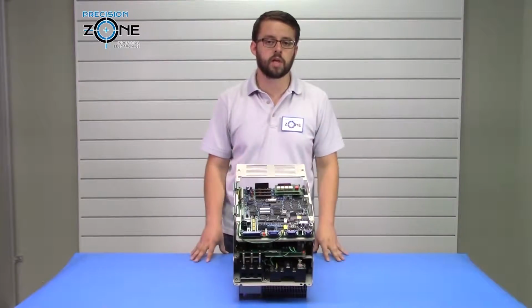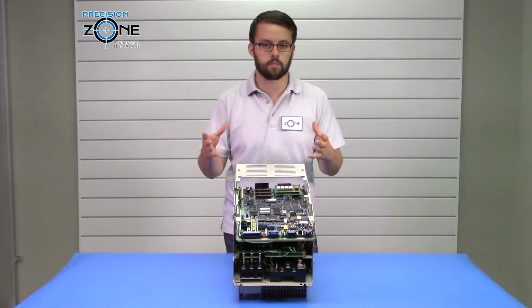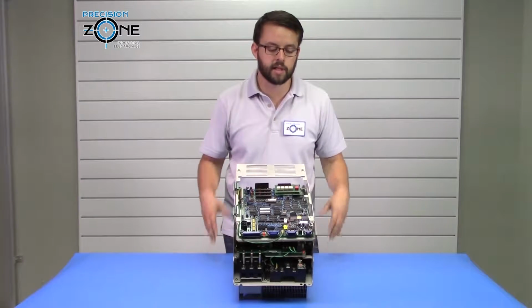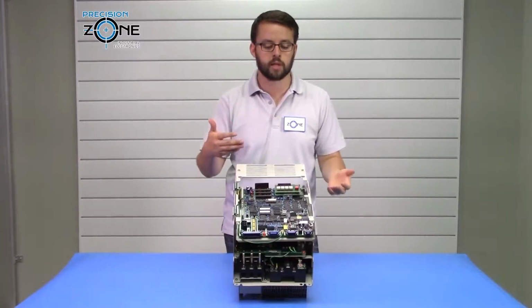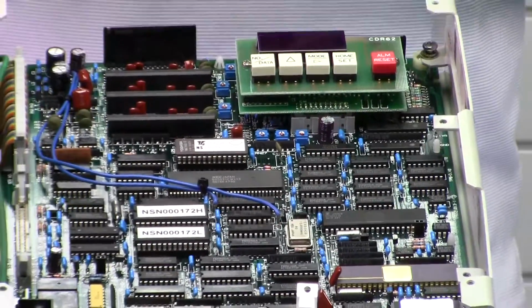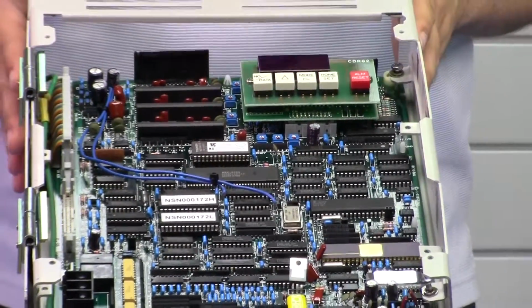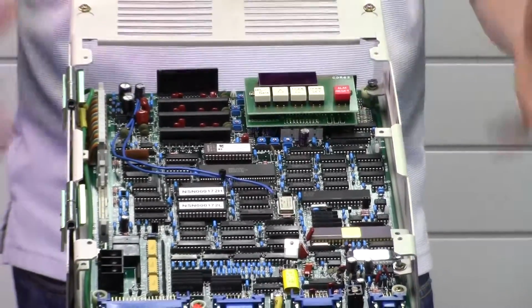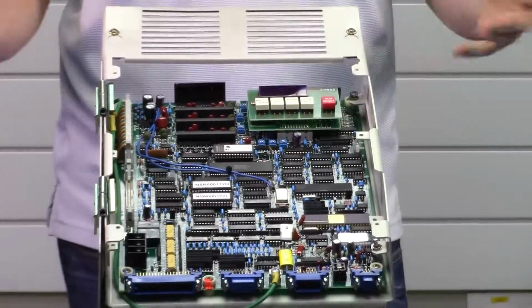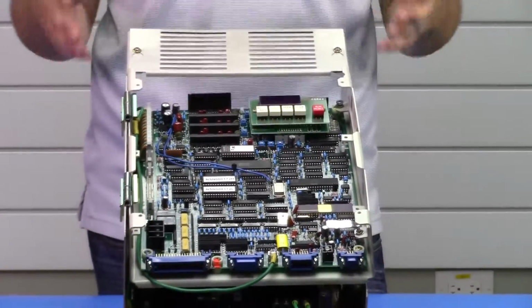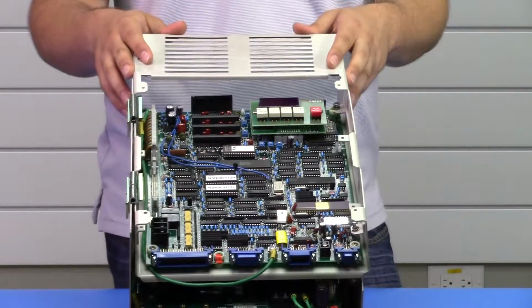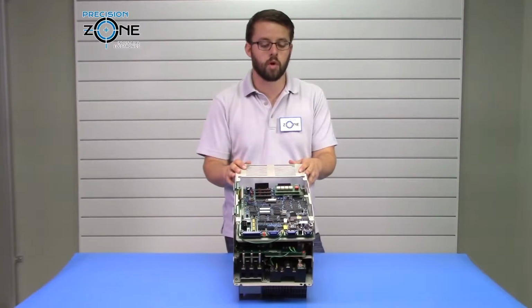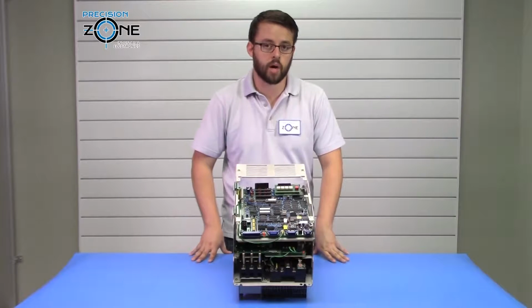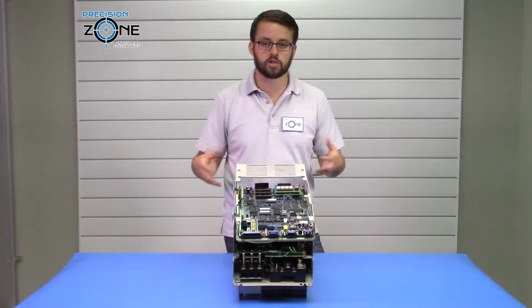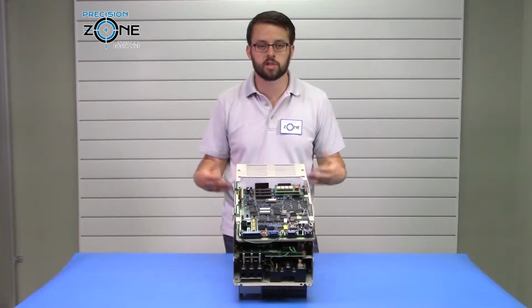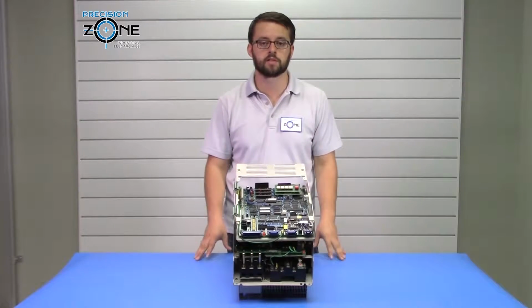The other PG alarm that you can get is just a PG alarm, which would indicate a fault in the connection between the encoder or the PG and the spindle drive. So you want to check those cables out in that case. For all encoder related alarms, you always want to verify that your parameters have been set correctly, and that the connections between the motor and the drive are also set properly. It could also be that the setup procedure wasn't done properly, so you want to check that as well.